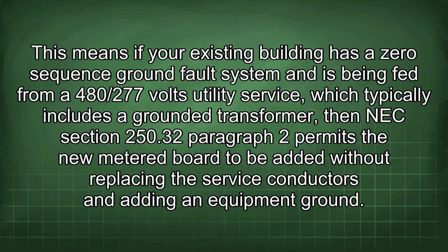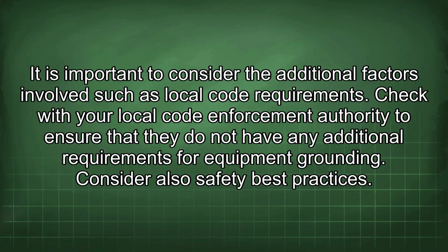480/277 volts utility service, which typically includes a grounded transformer, then NEC Section 250.32 Paragraph 2 permits the new meter board to be added without replacing the service conductors and adding an equipment ground. It is important to consider the additional factors involved, such as local code requirements. Check with your local code enforcement authority to ensure that they do not have any additional requirements for equipment grounding.